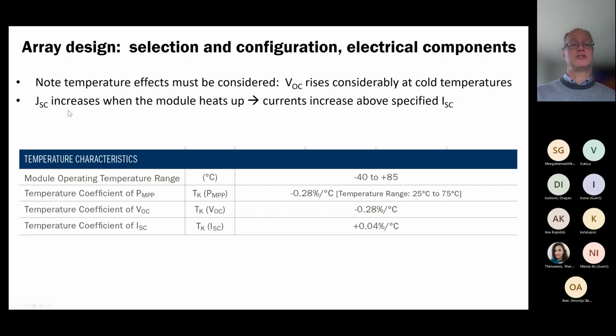Similarly, but really in the opposite direction, this should be I sub SC. The short circuit current will increase when the module heats up. That has to do with the semiconductor band gap effect primarily. Although it's true for silicon and for cadmium telluride that the band gap energy decreases with increasing temperature, it's not so clear that that's the same case for perovskite, for example, which is another technology that people are working to commercialize. So you need to take into account the hottest temperatures as well when you're looking at the maximum currents that are allowed. And these temperature coefficients are going to be provided on the module data sheet. And so that's where you can go to do these calculations.